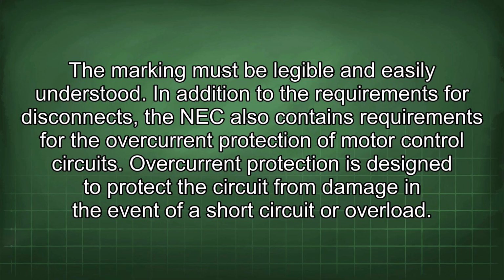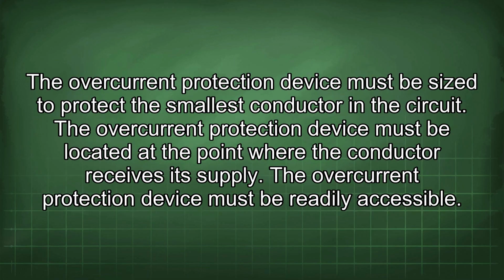In addition to the requirements for disconnects, the NEC also contains requirements for the overcurrent protection of motor control circuits. Overcurrent protection is designed to protect the circuit from damage in the event of a short circuit or overload. The overcurrent protection device must be sized to protect the smallest conductor in the circuit. The overcurrent protection device must be located at the point where the conductor receives its supply. The overcurrent protection device must be readily accessible.